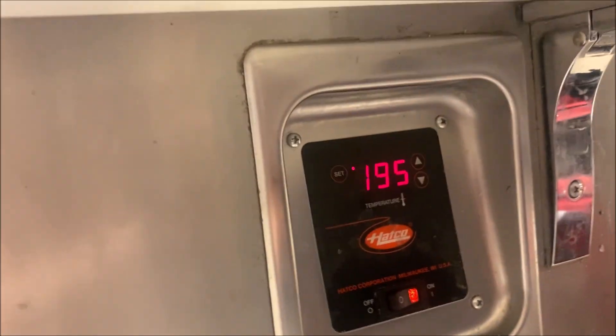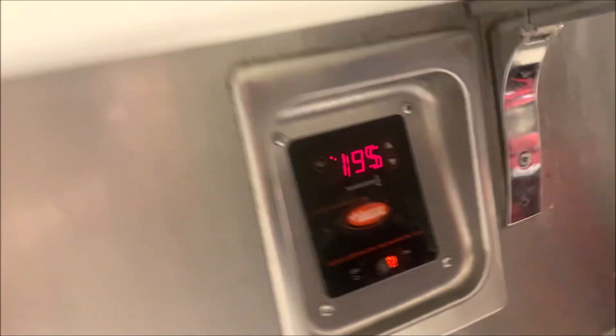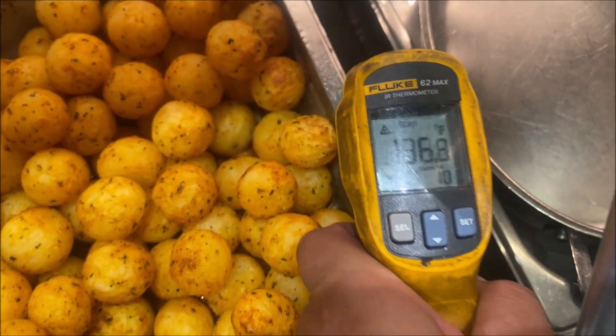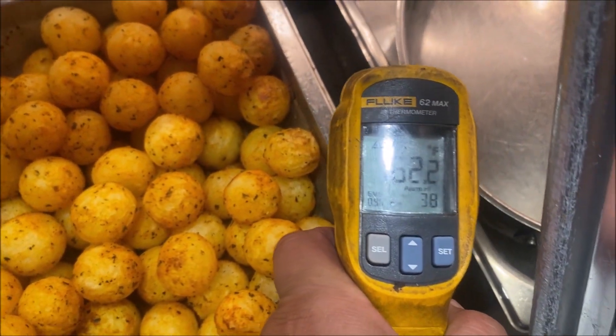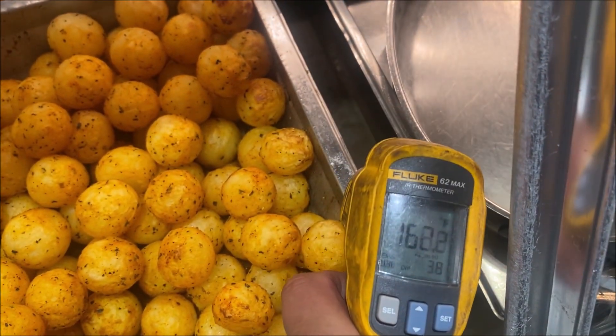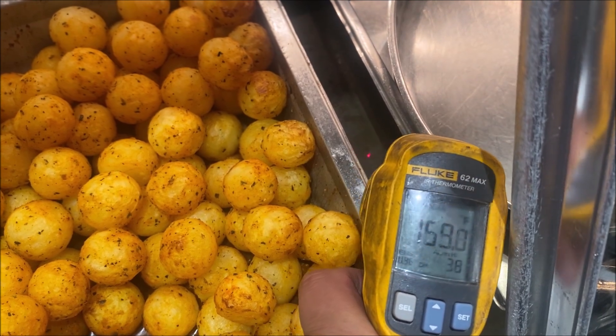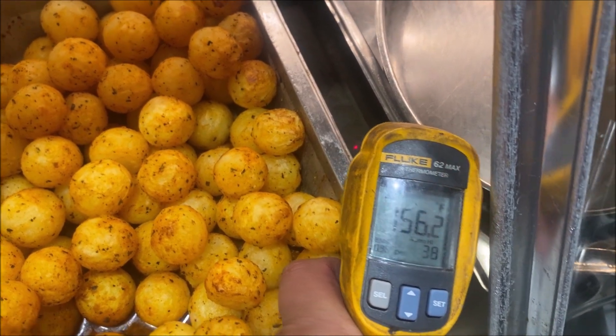And the last thing we're going to check here is just do a quick temperature check. So we've got set point 195. This probe is not super accurate. I just want to make sure we're not going over 200 degrees. So we're good there, 160, 170.